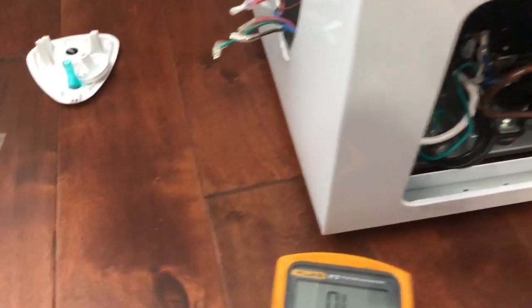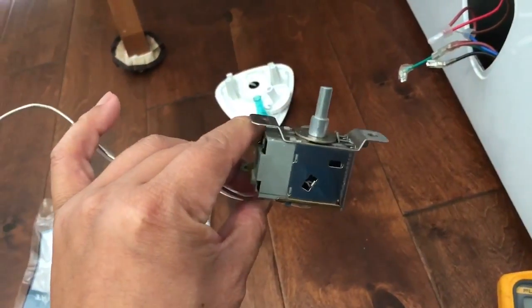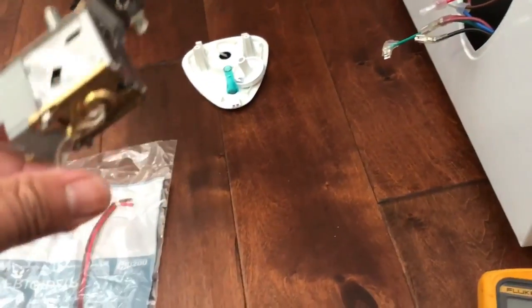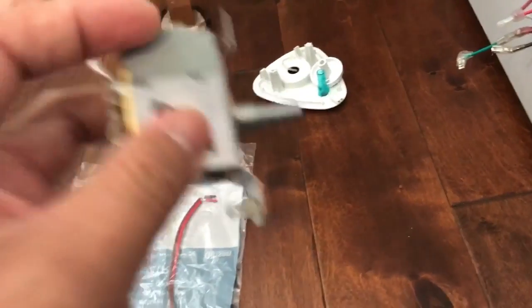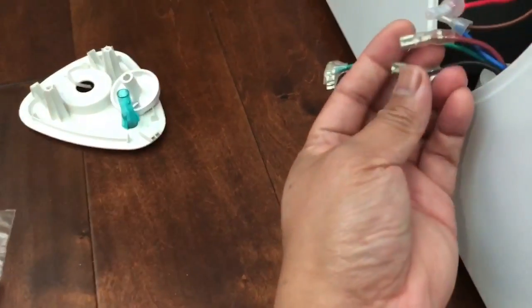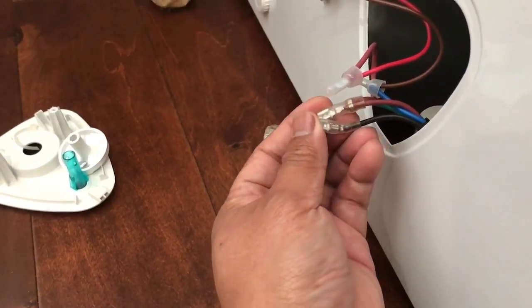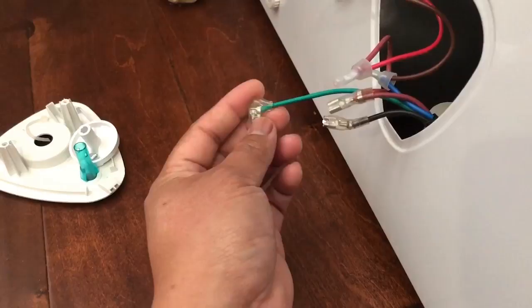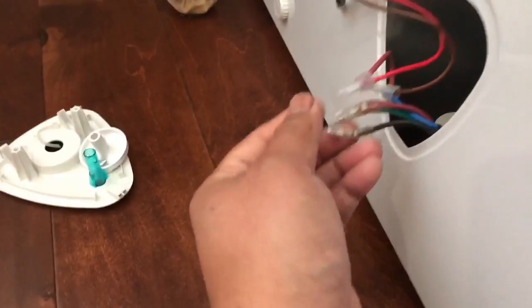The first thing you want to do before you purchase parts is to check and make sure your thermostat switch is good. What I did was take the wires connected to it — make sure you don't confuse the wires — and connect them together. It's the brown wire and the black wire. The green wire is the ground, and you can identify it because it's hooked up to the chassis or the frame.